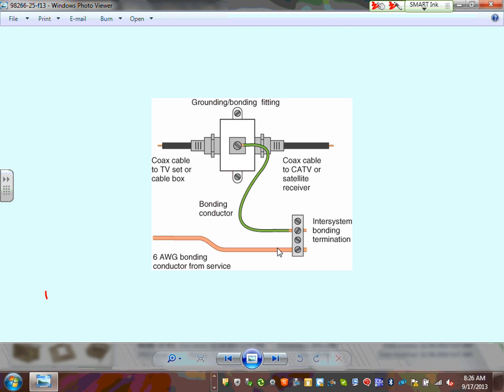So here's how you ground the shield. At the demarcation point, any shield that comes with any telecommunication cable must be grounded. That's conductor number 14, I believe, and that goes right in here - this is my demarcation point. You bring coaxial cable to the set or cable boxes, coaxial cable to satellite dishes, and you come right in here and ground it to the inter-system bonding terminal, or bonding jumper, the inter-system bonding terminal. Can you guys see how you have to take the shield and ground it?